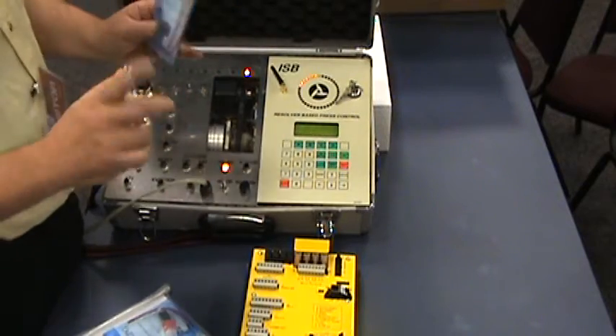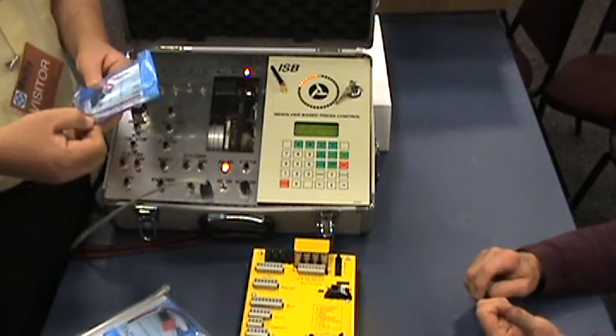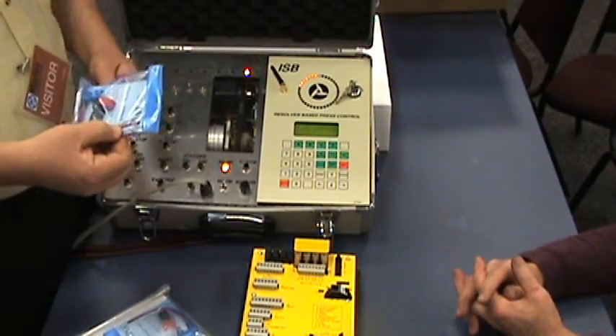Go to the actual physical safety valve, identify both the solenoids, and put these devices as close as you can to the safety valve. It's really important. And wiring it back here is not effective. You need to go as close to the safety valve as you possibly can. There's two of them because you have a dual safety valve. There's two solenoids. One side connects to the hot of the valve and the other side connects to the neutral. And put them there.